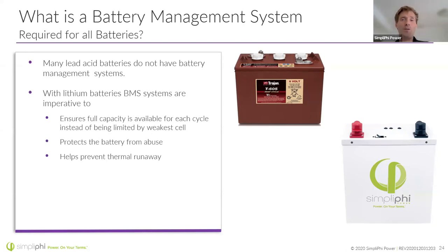Right? But if you've done systems with lead acid batteries, even deep cycle lead acid batteries, you know they don't last that long. Maybe 1,000 cycles for a decent lived battery. 2,000 has got to be close to max for a lead acid deep cycle battery. And you're very limited in how much you can discharge that battery. Most deep cycle batteries, we cycle them between 50% state of charge and 90. So you really have a small usable window.